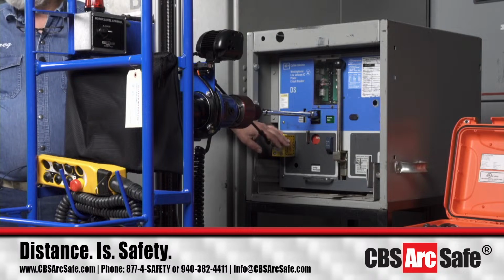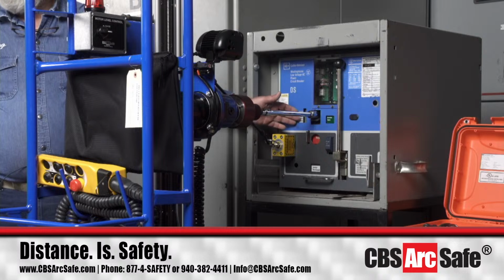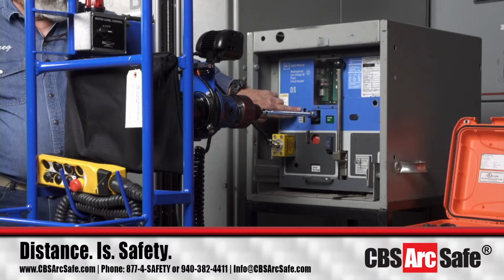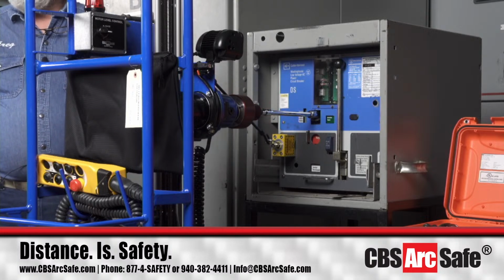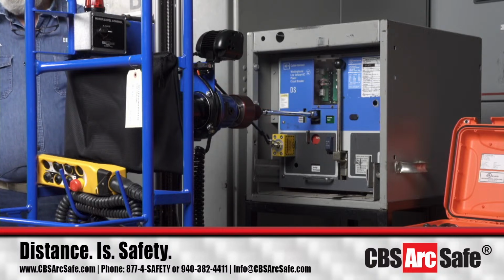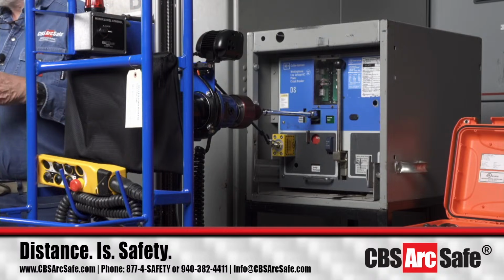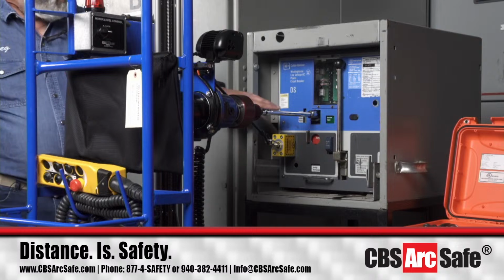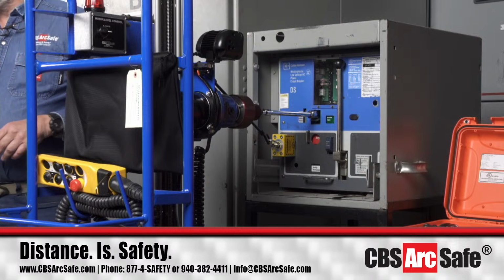So I just took the hand tool, I racked the breaker to where it was up in the connected position, and I made a mark on here to show where that was. And when we racked it back out and then they came back in the substation, we threw it in the cubicle, we hooked up the RS1 to rack it in. They say, it's not racked in all the way, because they were looking at the position of this tab and the word connect on here. I said, it's racked in all the way.